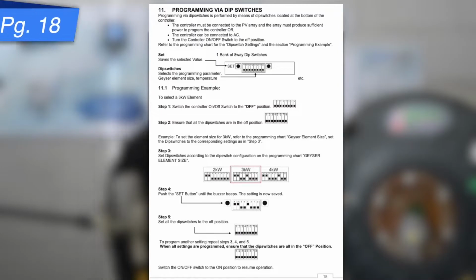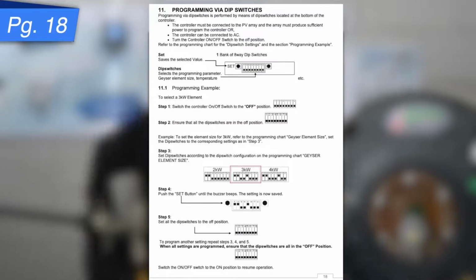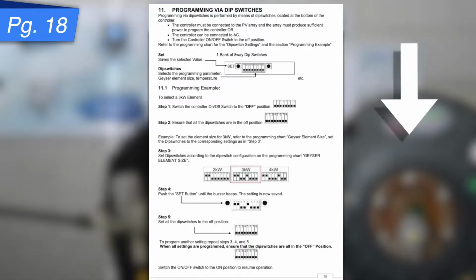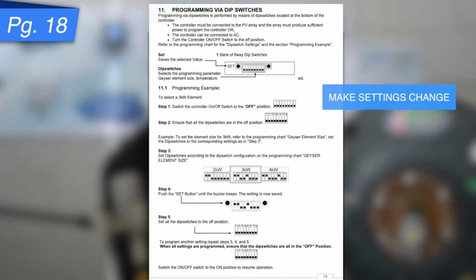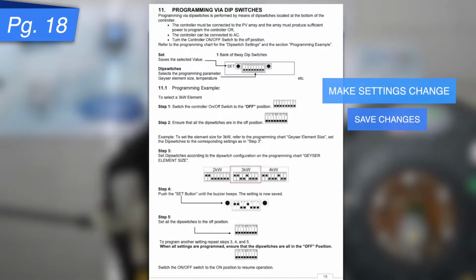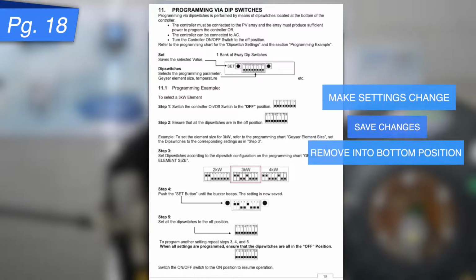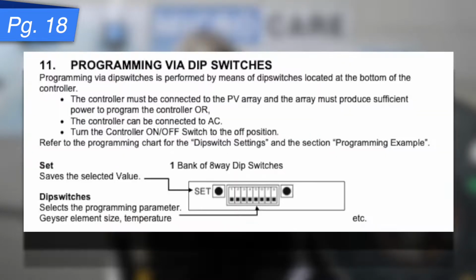For those of you who want to use the dip switches, on page 18, you'll notice that the dip switches are all in the downward position, and that is 100% correct. What happens is we make a setting change, we save it, and then we move it into the bottom position. This means that there can't be any problems down the line. So you'll see a diagram with a bank of the 8 dip switches, and either side of those switches are 2 buttons, and those are your saving buttons.